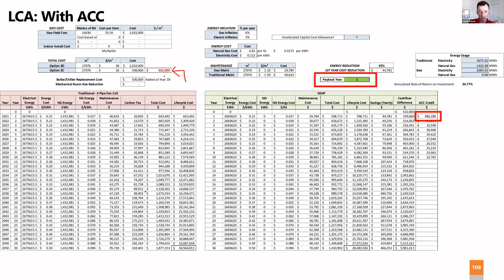The other thing we found once we moved into detailed design is because the geo design doesn't require the cooling towers, the chillers, and the boilers, we were able to reduce the size of the penthouse on the roof. And at $200 per square foot, we were able to shave $350,000 off the cost of the penthouse. So this upfront cost premium really went down to like $200,000.